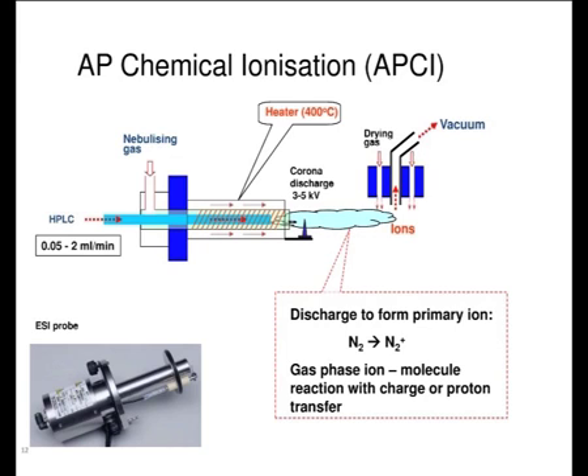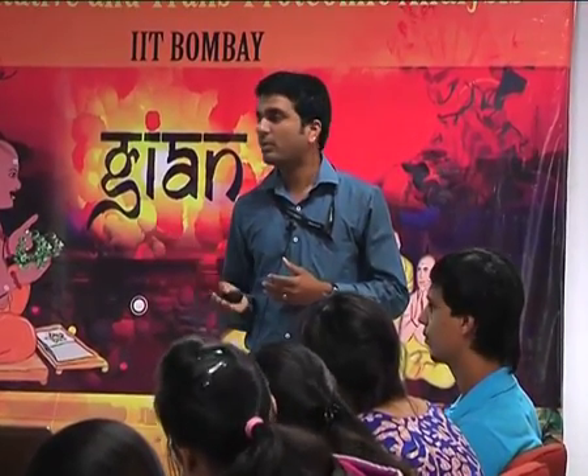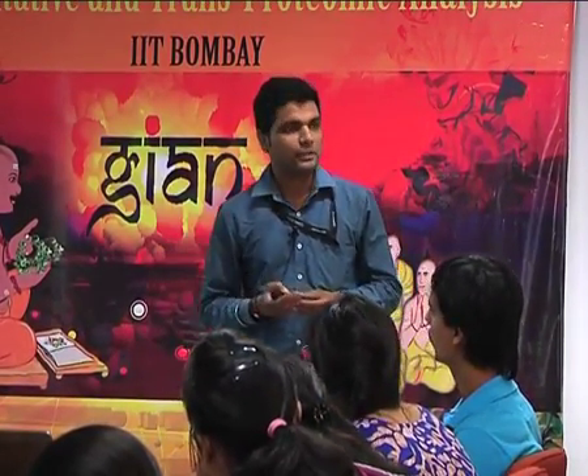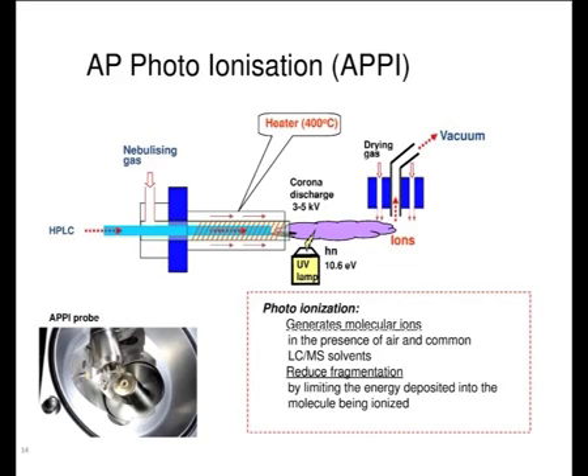For example, for steroids or vitamin D2, D3, this type of compound, we can use this technique for the ionization. Then APPI, atmospheric pressure photoionization. In this case, the technique is almost the same, but instead of the corona discharge needle, you are using a UV lamp at a particular frequency for the ionization of your compound. It generates molecular ions in the presence of air and the common LCMS solvent. They reduce the fragmentation by limiting the energy deposited into the molecule being ionized. Generally, this technique is used for the ionization of non-polar compounds.